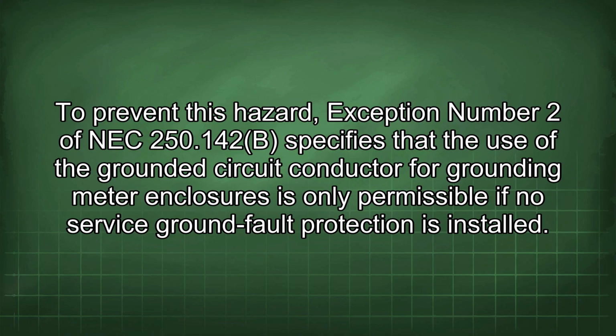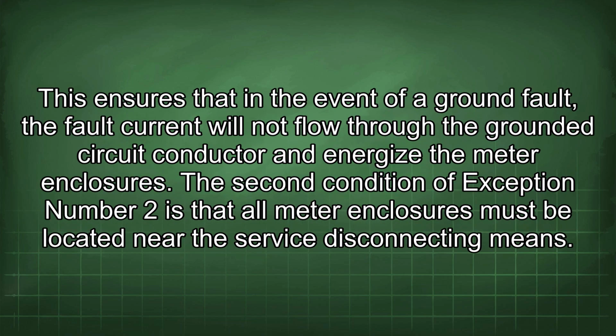To prevent this hazard, exception number 2 of NEC 250.142(B) specifies that the use of the grounded circuit conductor for grounding meter enclosures is only permissible if no service ground fault protection is installed. This ensures that in the event of a ground fault, the fault current will not flow through the grounded circuit conductor and energize the meter enclosures. The second condition of exception number 2 is that all meter enclosures must be located near the service disconnecting means.